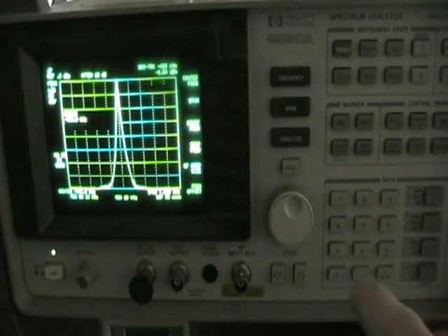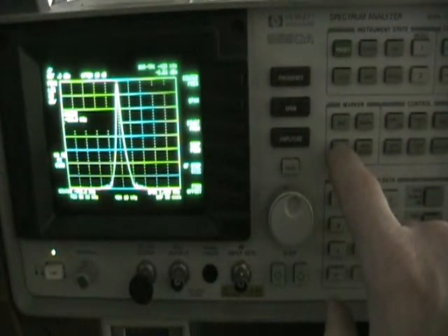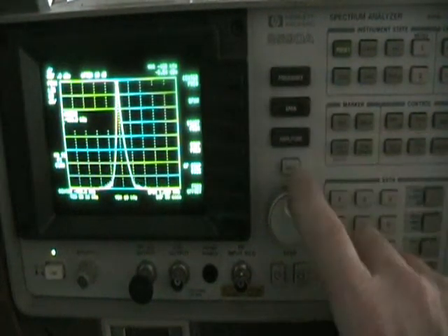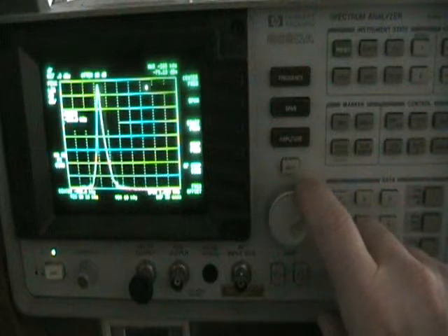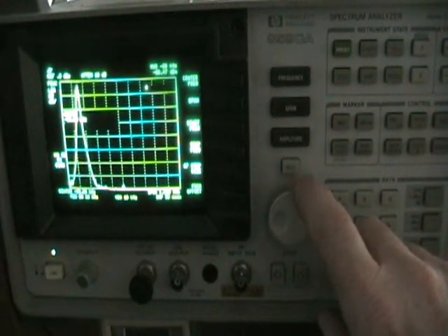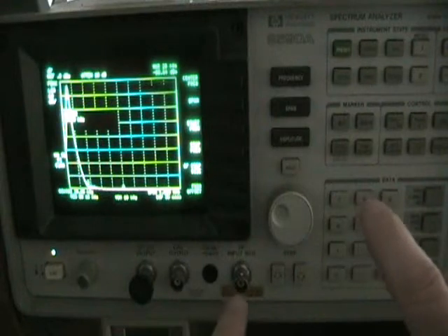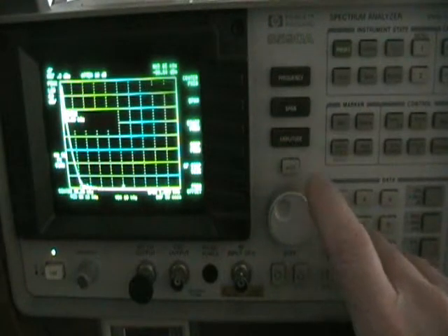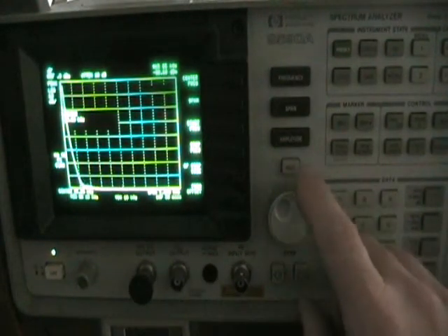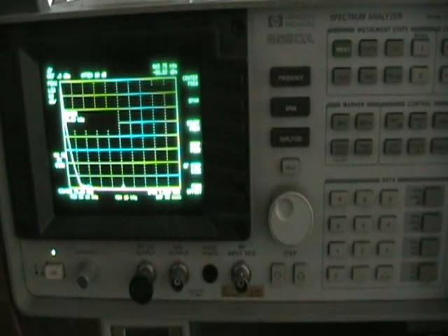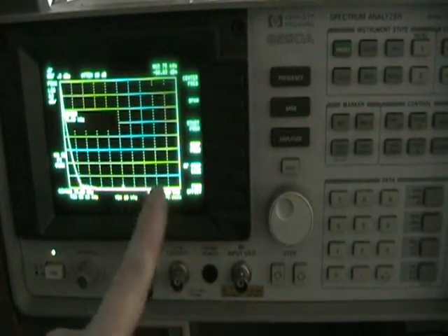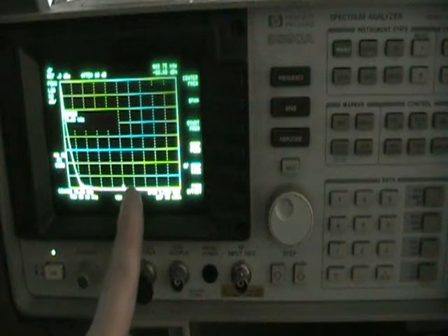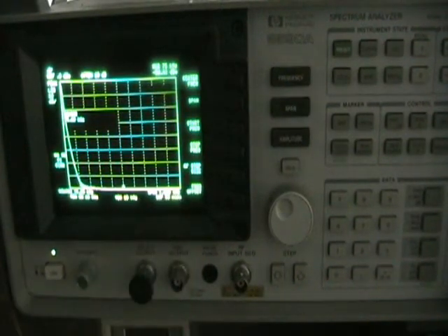This is what we will do. First off, we will turn off signal track. By turning off signal track, we can now move, by pushing frequency, the marker to the left. We know that this signal is a zero frequency marker because nothing is connected to the spectrum analyzer. So, if 0 is now on the left-hand side and the span is 1 megahertz, this means that the right-hand side must be 1 megahertz, and each square represents 100 kilohertz. 100, 200, 300, 400, 500, 600, 700, 800, 900 kilohertz, 1 megahertz.